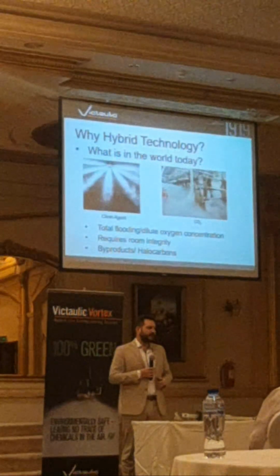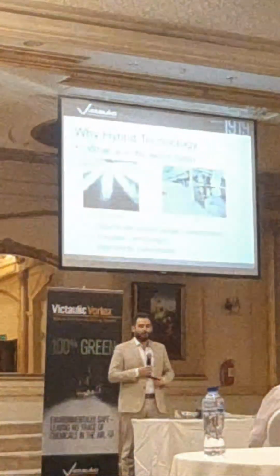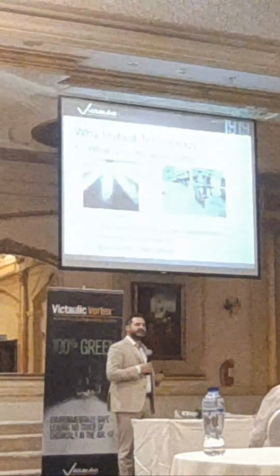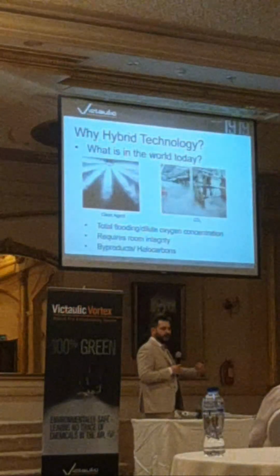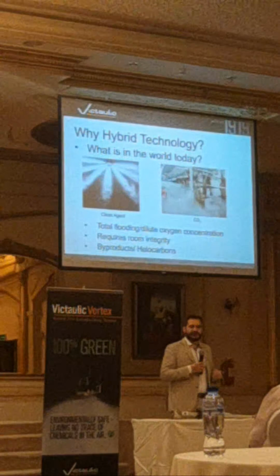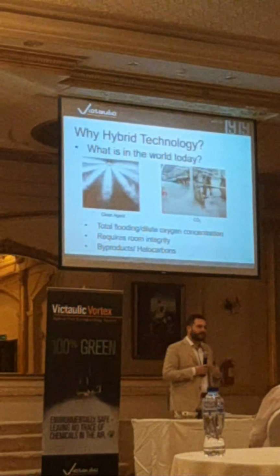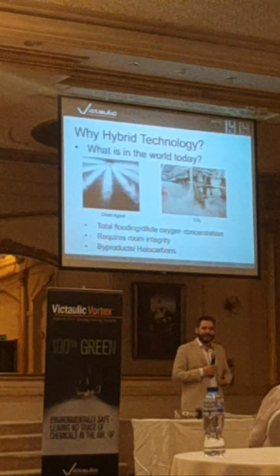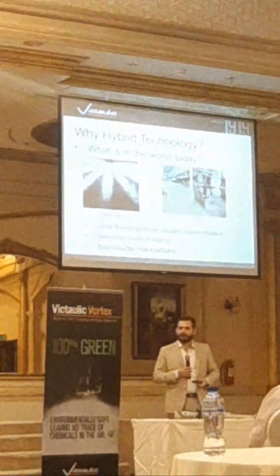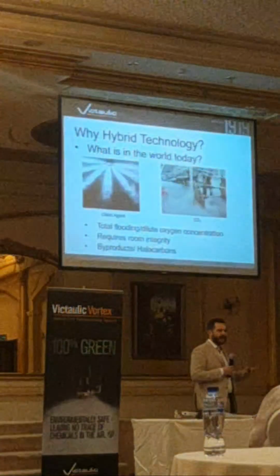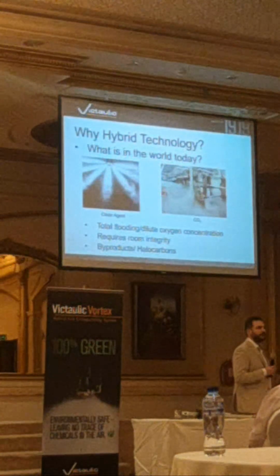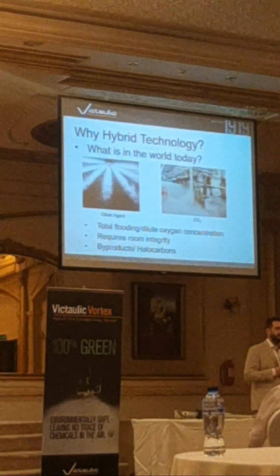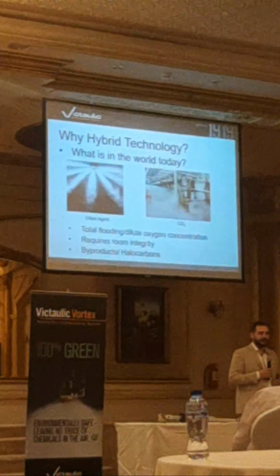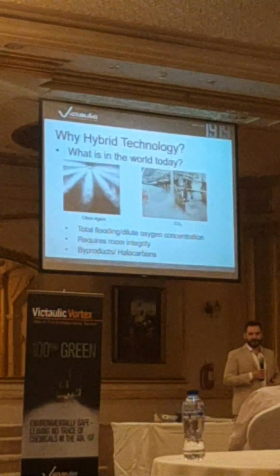The second technology that we're going to use is an inert gas, or just your clean agent, the gas system, where the concept is that we're going to add this into the room to lower the oxygen concentration down to a level where it is okay for people to remain in, but it is not okay for a fire. So a fire will be extinguished at around 16%. We will go down below that level, and it will be 12.5% of oxygen at the end of the discharge.